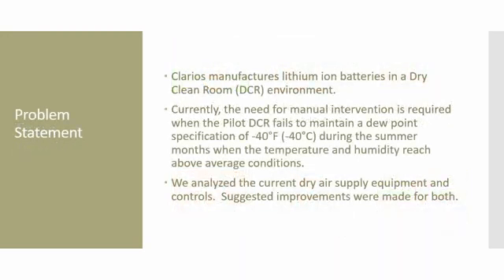Clarios, our project sponsor, manufactures lithium-ion batteries. This process needs to take place in a dry clean room. The current equipment requires manual intervention to maintain a dew point specification of negative 40 degrees Fahrenheit. This intervention is only needed during the summer months when the outdoor air is hot and humid. The Grand Valley State University team has been tasked with performing the analysis of the current dry air supply equipment and controls. From the analysis, we will make suggested improvements.